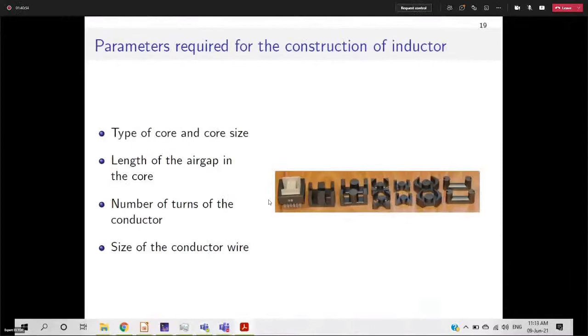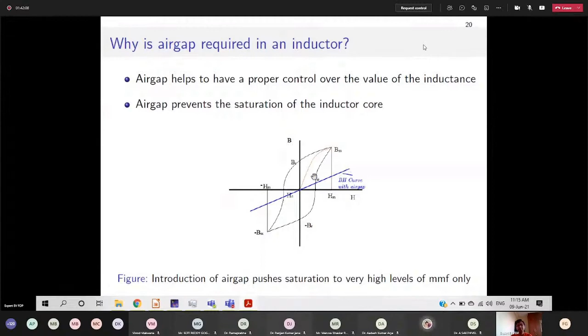So now the question is, why do you need an air gap in an inductor? As I mentioned, for a transformer, we don't want any air gap. We ideally want infinite magnetizing inductance. But for the inductor, we need an air gap because that will help us have control over the inductance value. If you don't put any air gap, then the reluctance of the core is so low that you might end up having a large number of turns to get the desired inductance value. Whereas a small air gap can help you achieve that very easily. And the air gap would also linearize the BH curve. It will push the saturation to a much higher limit, so in the operating range that we see, it is a linear curve, which is definitely better for operation.